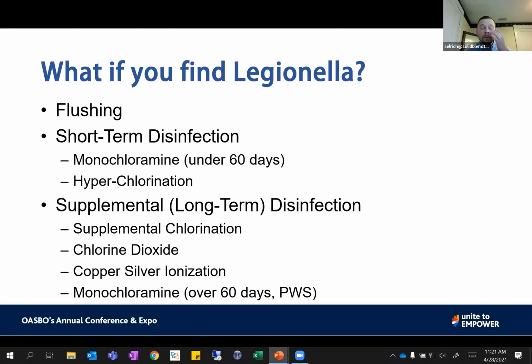With the hyperchlorination, we come in and inject a very strong percentage of bleach into the incoming water main. And we're going to pull that through the entire system. We're going to verify that we've got the disinfectant at every single fixture in the building. We're going to log that. We're going to soak it for a period of time. And then we're going to flush that system all the way back down to regular city water levels, verify that. And then we wait about 48 hours and we do a retest to verify that it was effective.